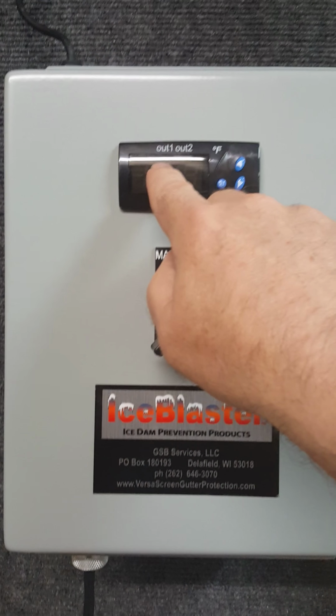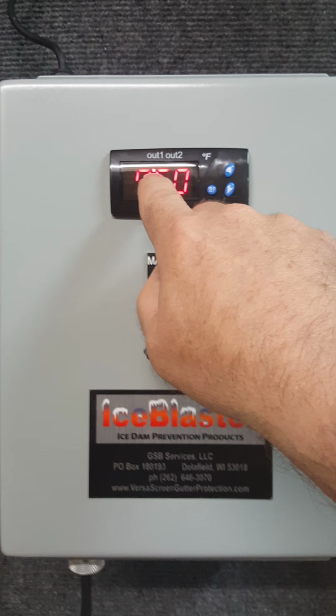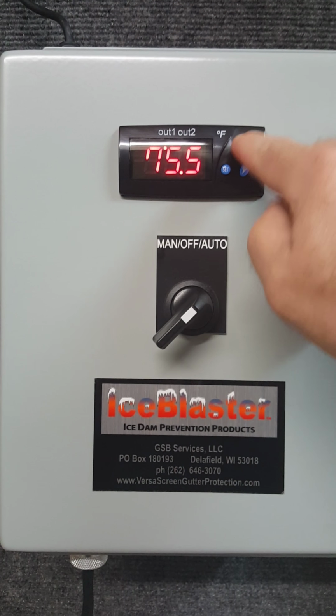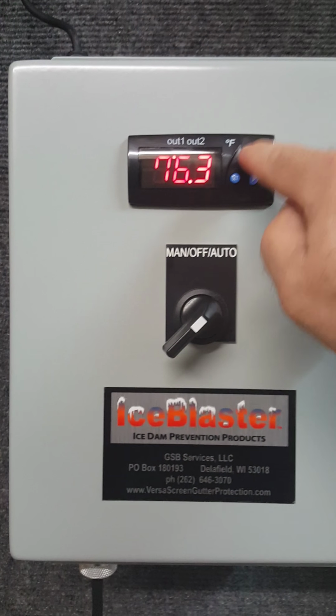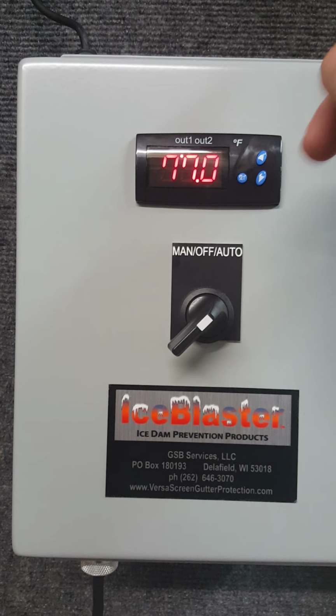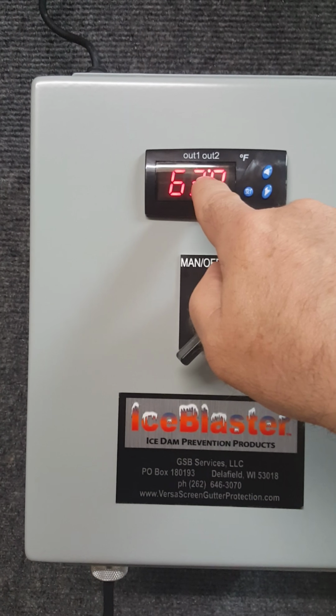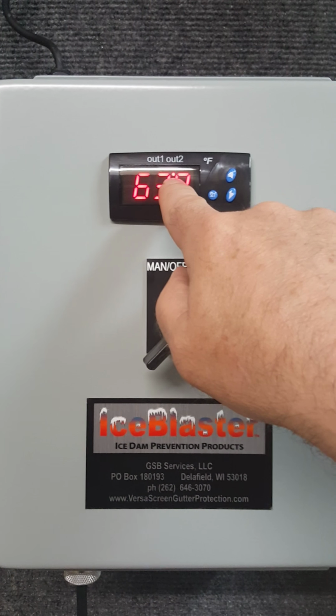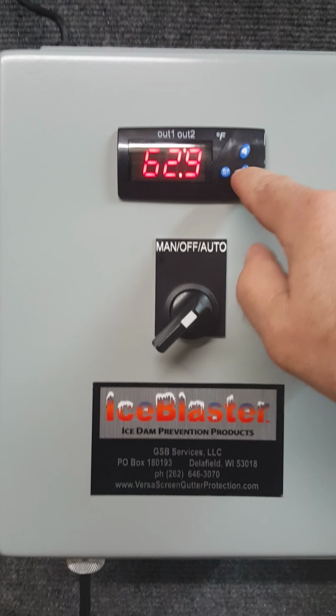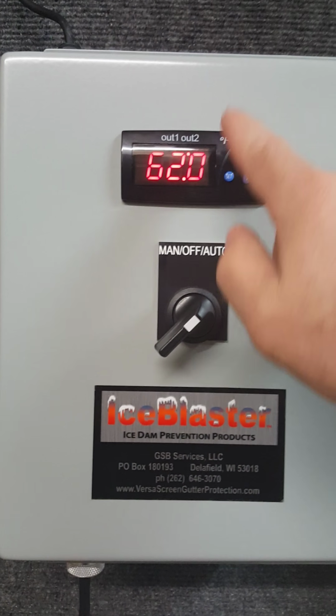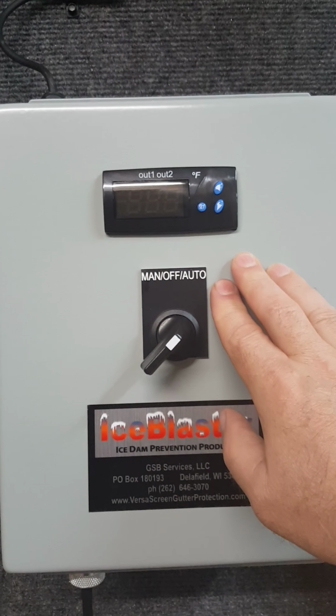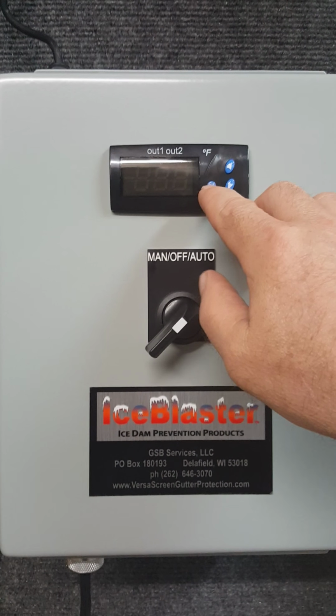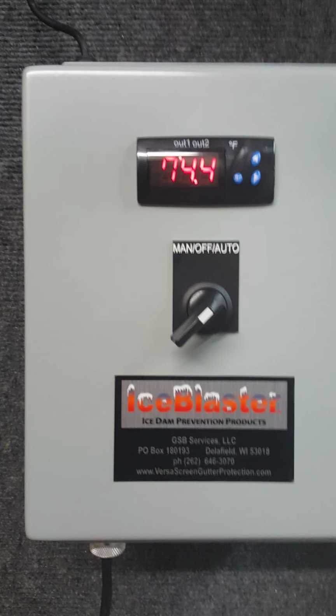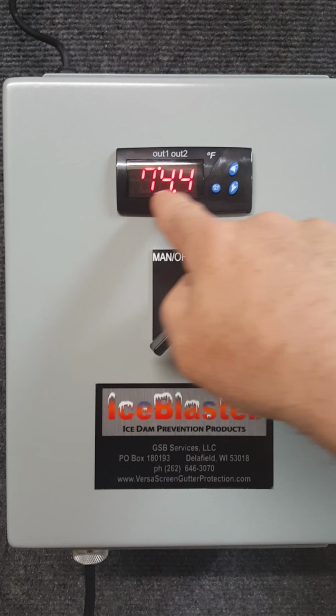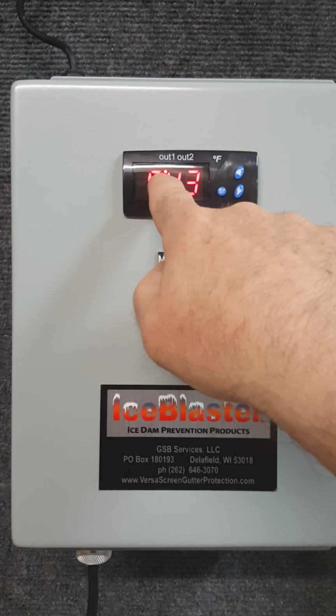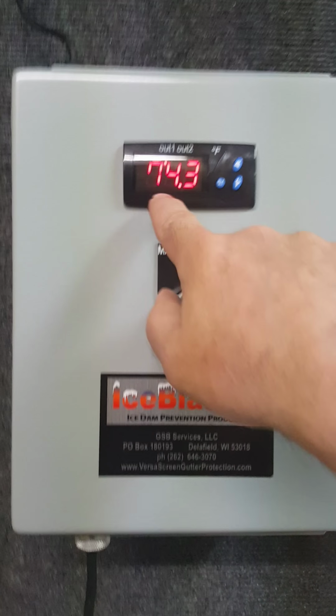The first setting is under Out 1. You'll see the little dot there under Out 1, and that allows you to arrow up and arrow down so that you can fine-tune it. Then hit set again, and that'll bring it over to Out 2. It's flashing, so you can see you can arrow up and arrow down with that. Now we've just got these set for the temperature range that we're in now, so we can see things working. If we look at it, we've got that set point up above the ambient temperature, and so you see the light on, it's reading temperature.